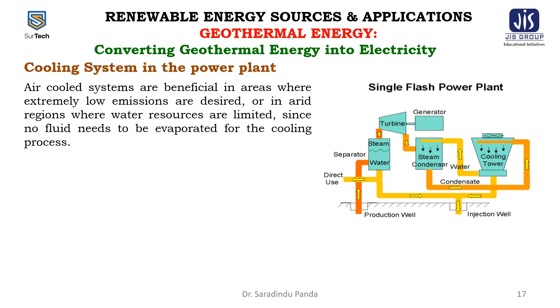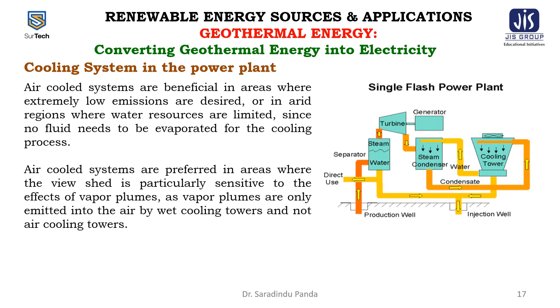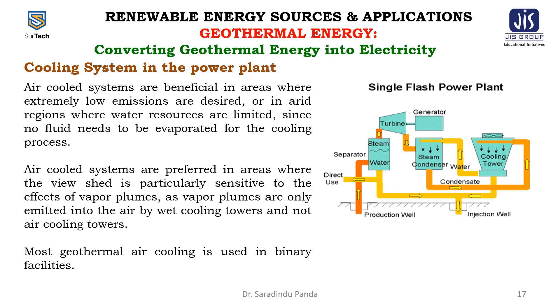Air cooling systems are beneficial in arid areas where extremely low emissions are desired or where water resources are limited, since no fluid needs to be evaporated for the cooling process. Air cooling systems are preferred in areas where the viewshed is particularly sensitive to the effects of vapor plumes, as vapor plumes are only emitted by wet cooling towers and not air cooling towers. Most geothermal air cooling is used in binary facilities.